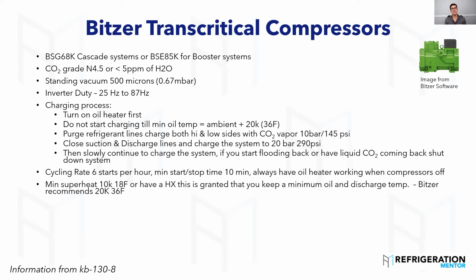Different manufacturers have different designs. I know in Advansor, they'll have a loop for the low temp going in through the flash tank receiver to make sure they're always staying above 20K or 36. Oil temperature, I want it at 30C or 86 degrees Fahrenheit. Absolute minimum 20C or 68 degrees Fahrenheit. When you start to get your oil that low, there's something going on. There's going to be dilution happening because your oil's so cold. Why is your oil so cold? If your oil is that cold, that means the return gas, that suction gas coming back, is super cold. So you need to understand why that is happening. It's pretty cool that they put this in here, because I don't see it in a lot of manufacturers' manuals.